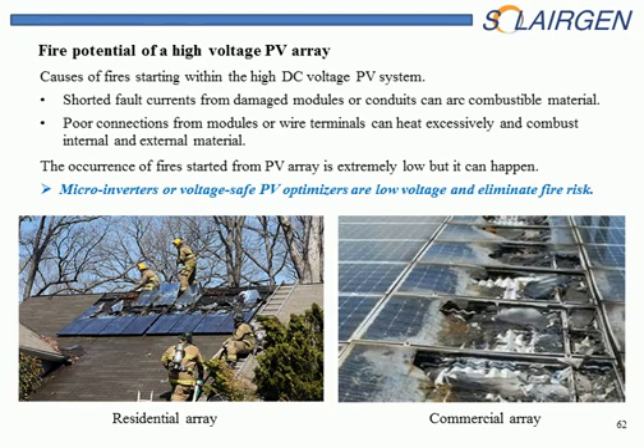If these are microinverters, the potential is minor. You can just turn off the AC power and you're down. If it's a string inverter, an older string inverter with high voltage, then there is a little bit of potential up there. So if you're hosing it down, there could be electricity at that location, so just be mindful of that. This is not a common occurrence, but it has happened. The potential is there. The newer systems are safer, less likely for this to occur. Older systems had a little bit of an element of risk involved in it, so this did happen occasionally.